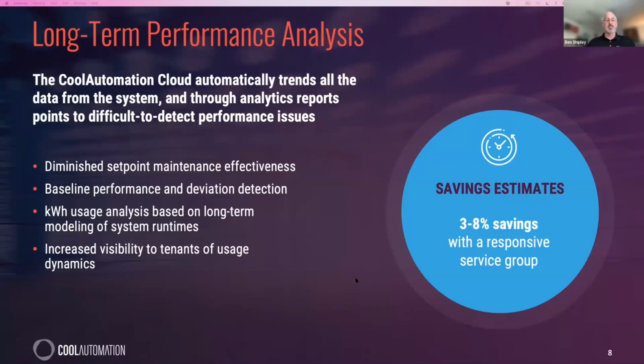With that, as well as looking at any baselines - we talked about amperage, but there are other baselines you can be looking at - and looking at any deviations over longer periods of time. Looking at the overall kWh usage on each of the indoor units in the VRF space is also going to be very helpful, particularly if the schedules and set points remain consistent month to month, year to year. Any kind of deviations in the kWh will raise a flag.